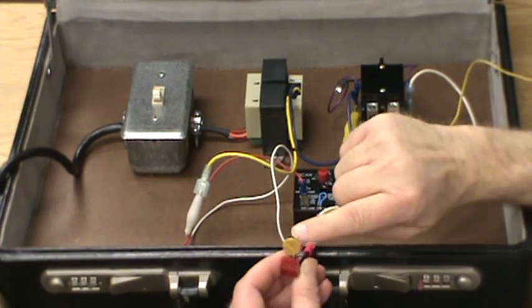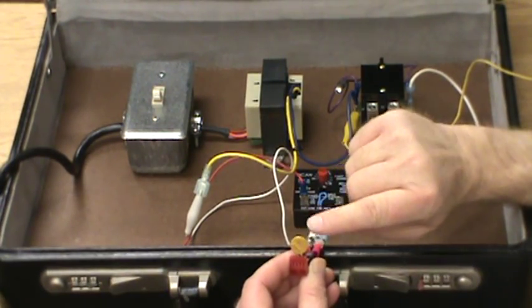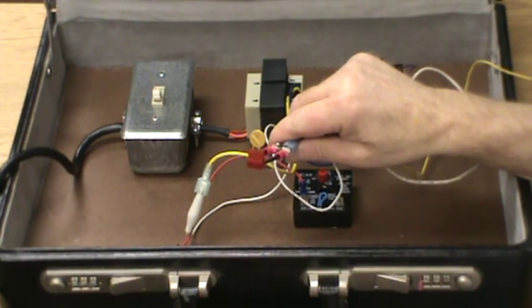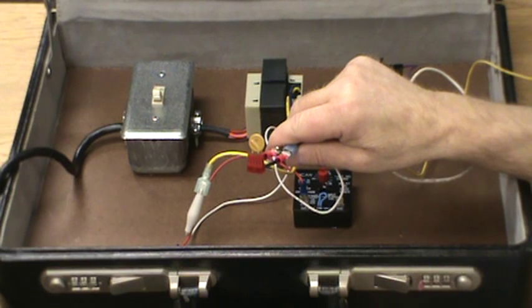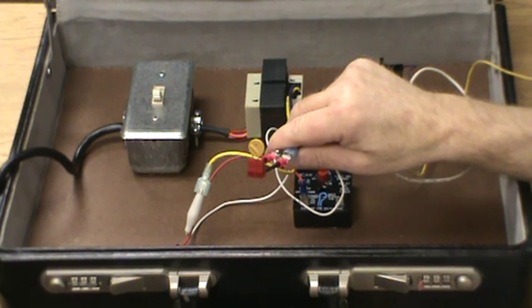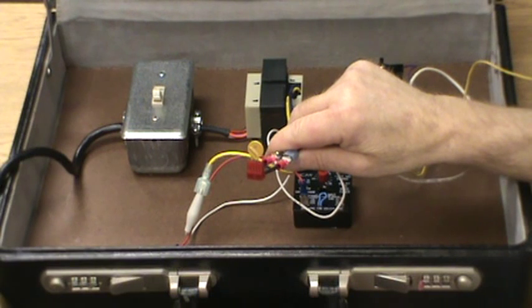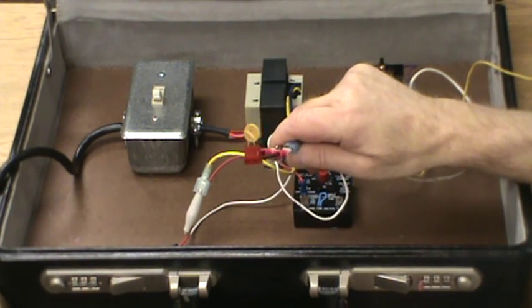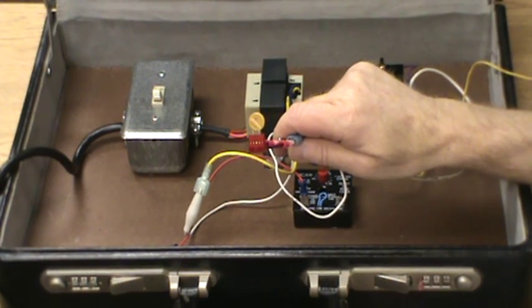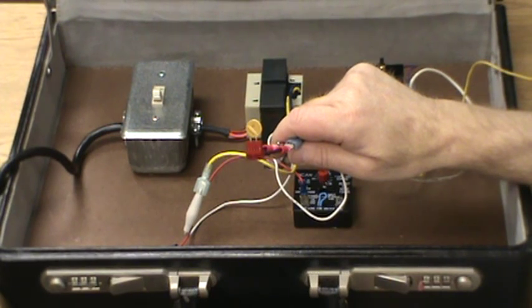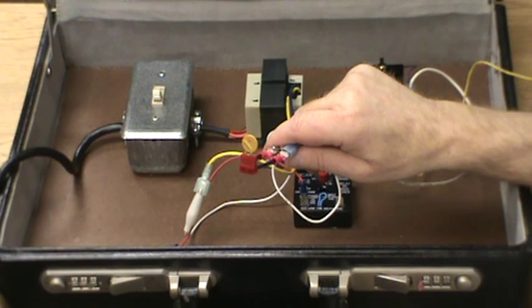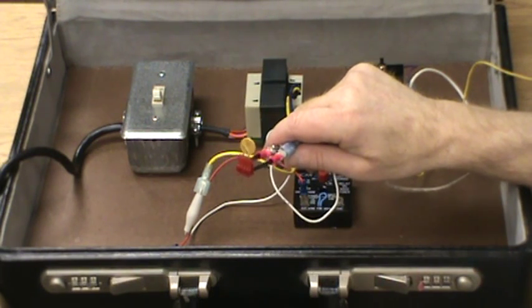Basically, one fuse fits all. This particular fuse is sized up for a 40 VA transformer - this little round disc right here. It'll replace about five or six different types of fuses that are on these 40 VA transformer systems, so this is basically the only fuse you need to stock on your truck that replaces all six styles of fuses for the 24-volt secondary side.